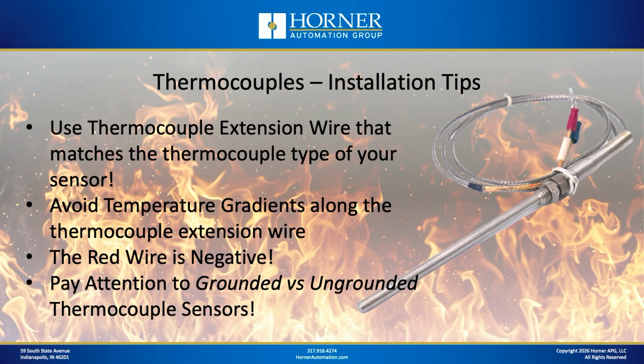Okay, let's go through the installation tips now. Now we're going to talk about that extension wire. You need to make sure that the wiring that's used all the way from the probe, all the way back to the PLC or wherever the measuring instrument is located, all that wire needs to be of the same thermocouple type and thermocouple extension wire type of your probe. Okay, that's critical. Otherwise, you're going to have cold junctions out in the field that are not compensated for, and you're going to have very inaccurate readings. So that's why it's important to understand the thermocouple effect when you have to apply thermocouples.